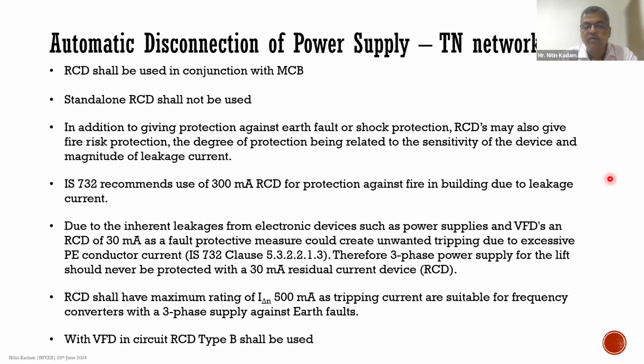Okay, now there is also a misunderstanding where people think that a 30 milliamp RCD has to be used on the elevators where you have a VFD, or variable frequency drive. Now, if you connect a 30 milliamp RCD on the variable frequency drive, it is going to trip as and when the elevator starts. It will cause unwanted callbacks on the elevator equipment, and therefore this is not to be used on the elevator with the variable frequency drive.